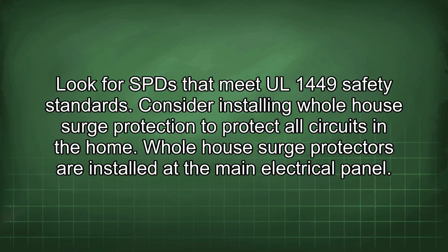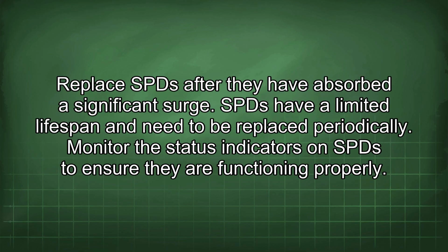Consider installing whole house surge protection to protect all circuits in the home. Whole house surge protectors are installed at the main electrical panel. Replace SPDs after they have absorbed a significant surge. SPDs have a limited lifespan and need to be replaced periodically. Monitor the status indicators on SPDs to ensure they are functioning properly.